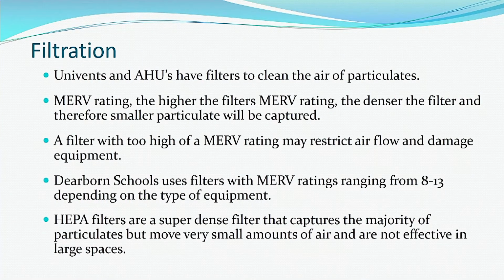Filtration. All of our air handlers and univents will have some filter banks to filter and clean the air as it passes through these air handlers and equipment. Filters are all rated with something called a MERV rating. The higher the MERV rating, the denser the filter and the more particulates it will capture. A filter with too high of a MERV rating can be a problem on much equipment because we can actually end up restricting airflow and getting less of the outdoor air that we want.